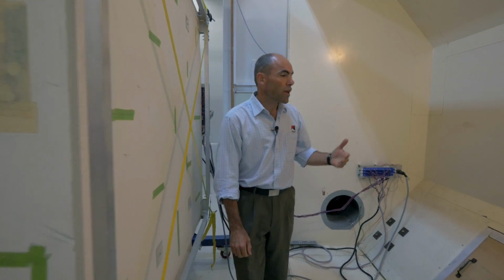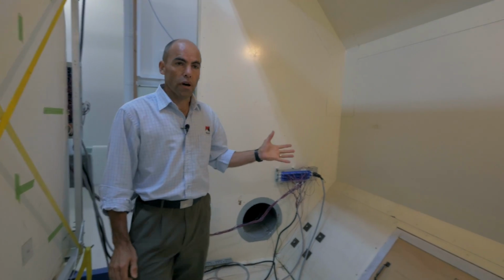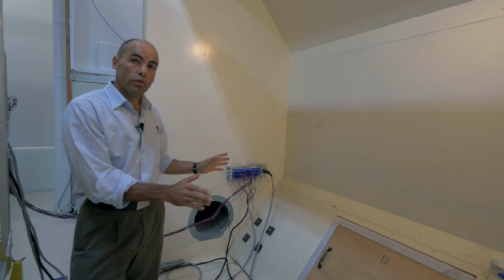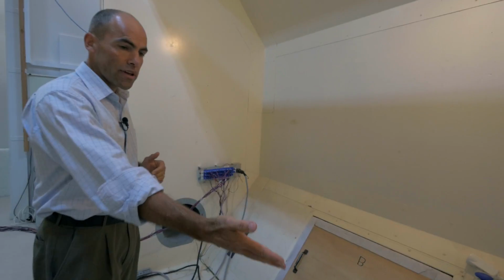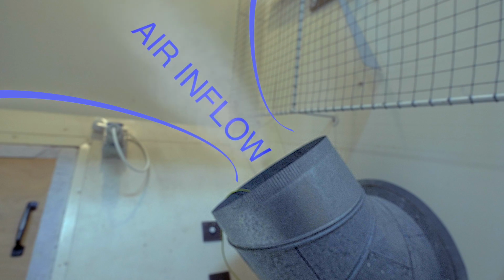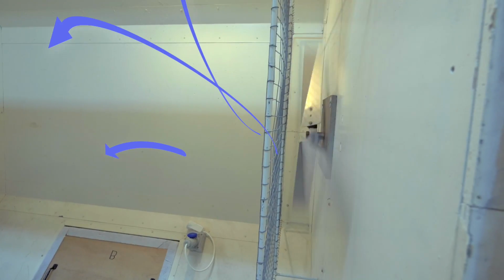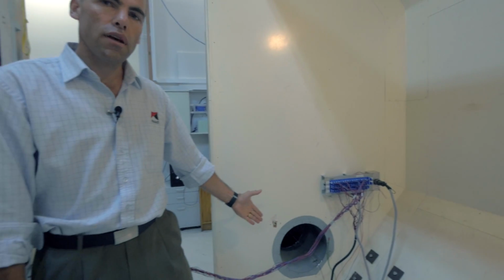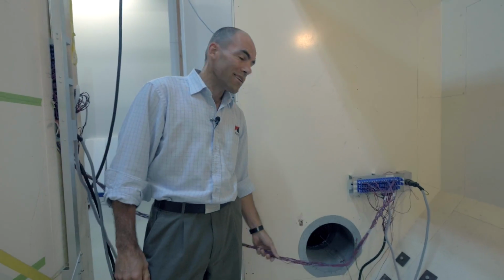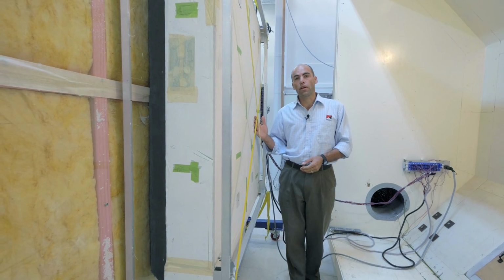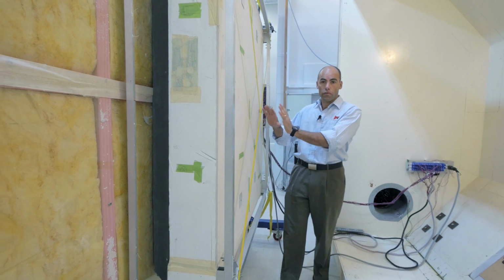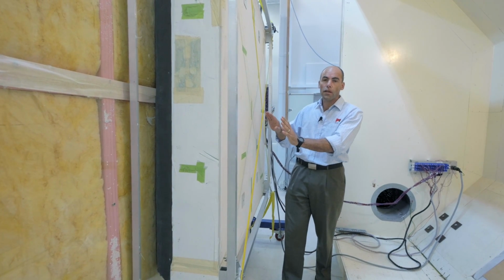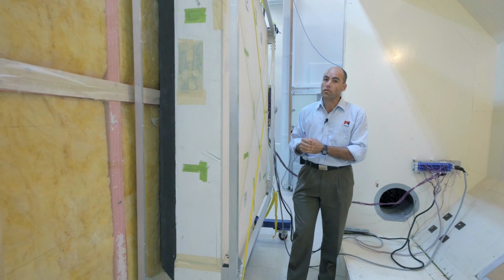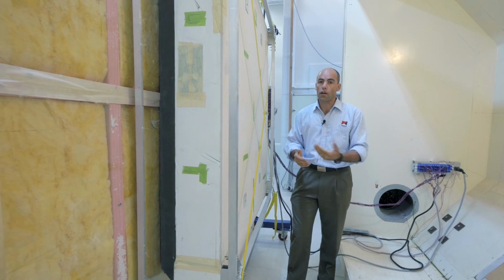On the other side we have our warm side. Over this side we have air at 20 degrees. The air will be coming in through the ducting over here, and our mixing fans make sure we get a constant flow of air, and the air disappears out through here, as does all our data. All the data it collects from here, it's got thermocouples and thermopiles inside this area here. Now that all travels out through to the data acquisition system.